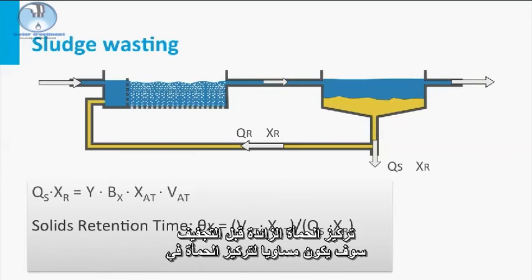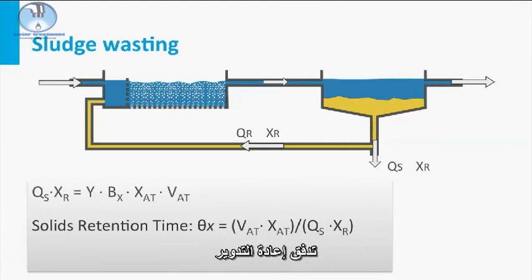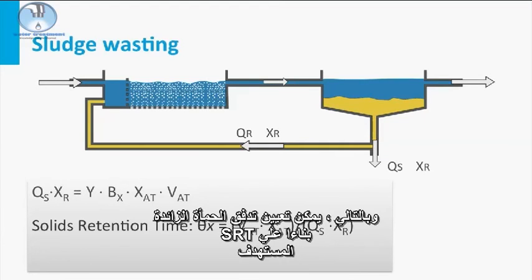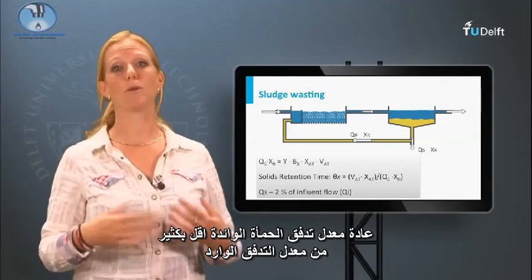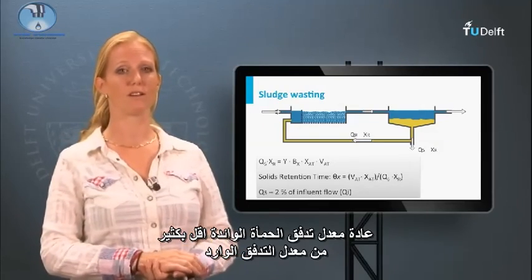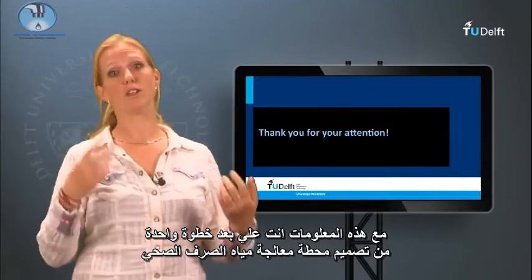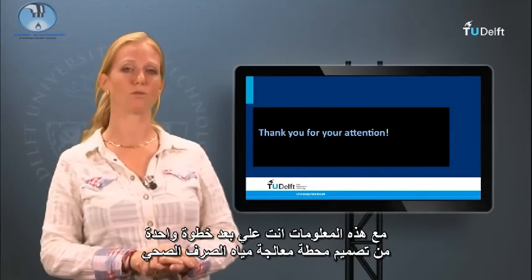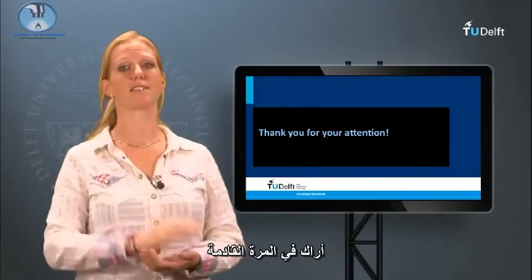The concentration of the waste sludge before thickening will be equal to the sludge in the recycle flow. Therefore, the waste sludge flow can be set based on a target SRT. Typically the waste flow rate is much lower than the influent flow rate. With this information you are one step further in the design of a wastewater treatment plant. See you next time!